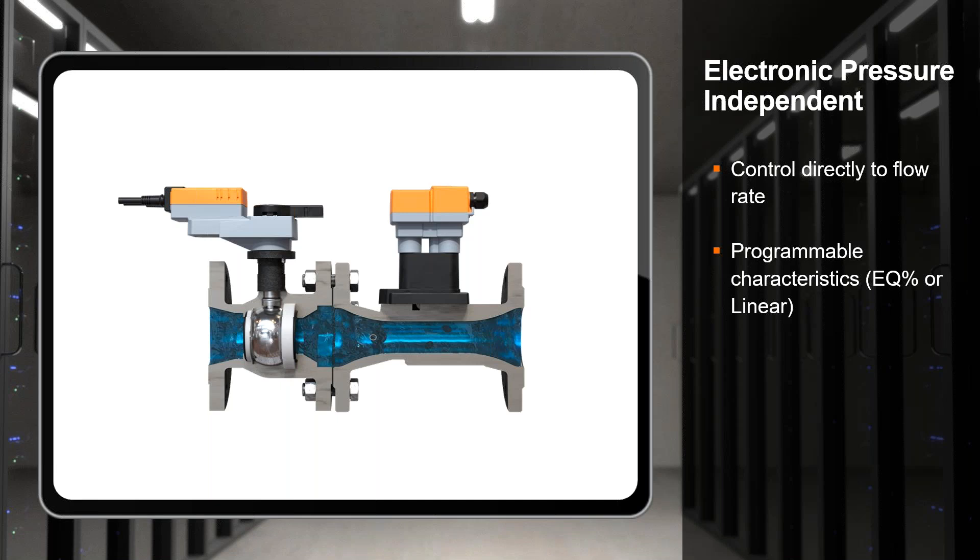The other thing that's interesting about this valve is that it has a programmable characteristic. If you're familiar with control valves, you know that typically they have what's known as an equal percentage flow characteristic. This is an exponential curve that allows the valve to open quite slowly and then have a much higher curve flow rate as we get the valve more open. This is the opposite behavior of how coils work and so it makes a good match for a coil. However, if we're trying to control specific flow rates or fixed flow rates, we can reprogram this valve to be linear so that if you make a 10% change in the control signal, you just get a 10% change in the flow rate.